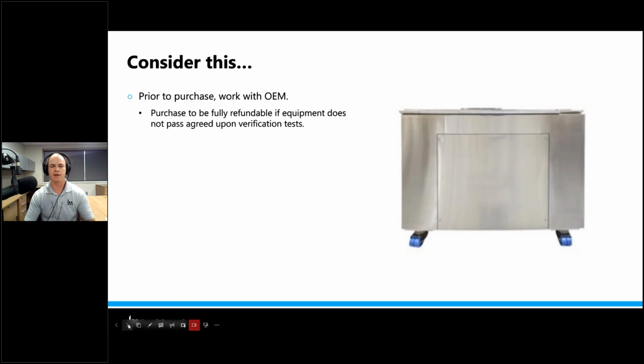And so another thing to consider is ultrasonic cleaners are a huge investment. It's a huge capital investment for your team, and you shouldn't ever take capital investment lightly. So something to think about is when you are in the beginning stages of planning a purchase, work with the OEM and have an understanding in writing that, hey, we're going to test this thing with these tests, and if it does not pass these tests upon installation, then we should be fully refunded for this equipment because it's not functioning, or it has to be reserviced or what have you. But as a brand new piece of cleaning equipment, it should be able to pass these agreed upon tests. All right, so that's just something to consider to cover your big investment, if you will.